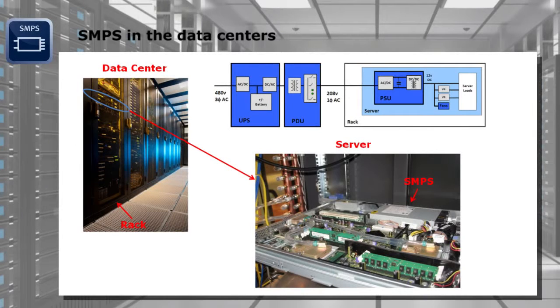How does a data center in reality look like? Let's start from a theoretical block diagram, starting from a 480 VAC three-phase input, followed by a UPS stage including a battery pack, and then a power distribution unit including a transformer for the required galvanic isolation, and then protection devices against overcurrent or overload, typically electronic breakers.